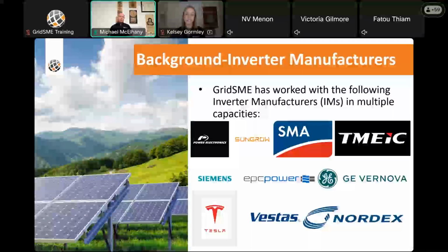And so one of my roles is when the plant gets to bucket 3, and we need to have the control protection settings reviewed by CAISO, as well as the attachment A and the inverter settings report, that's when I get involved. We get a lot of information from our inverter manufacturers. I've got 4 of them that have provided me in the last week some additional information that's going to be content for this particular presentation as well.